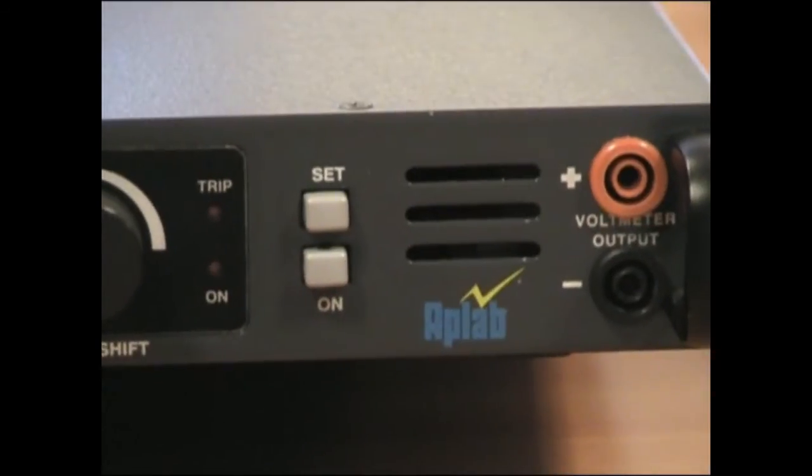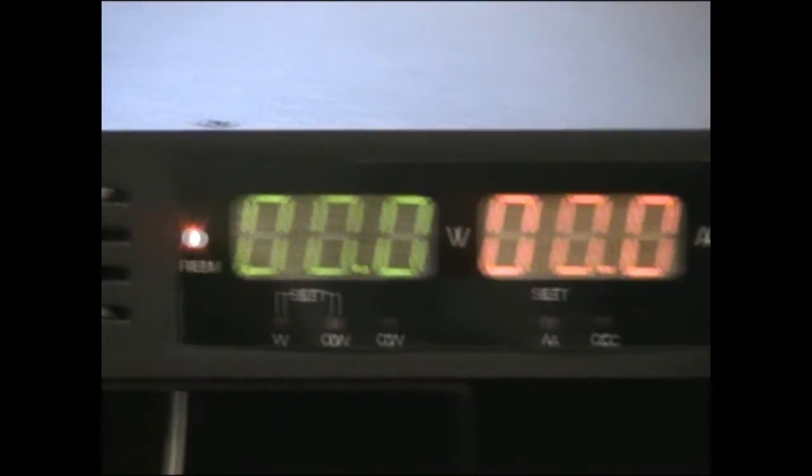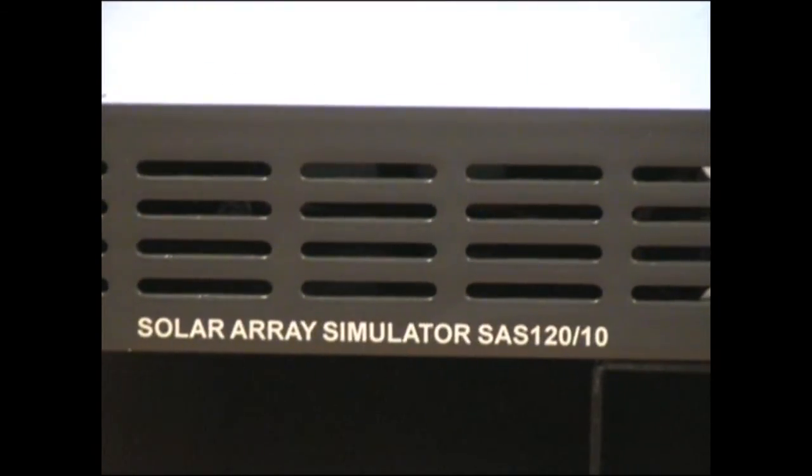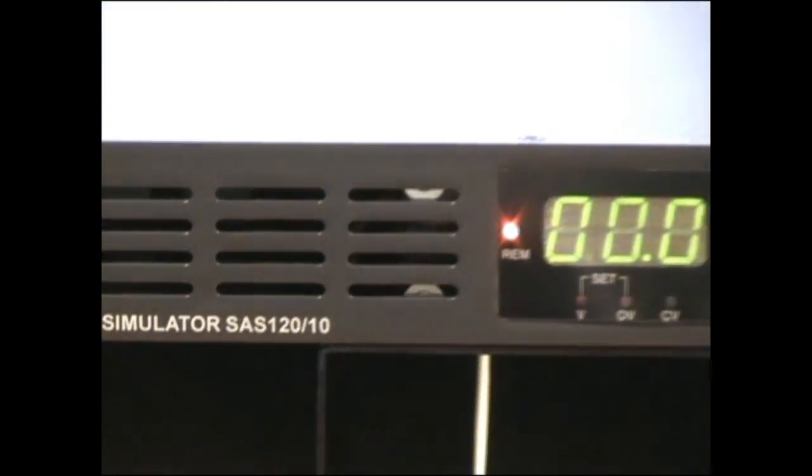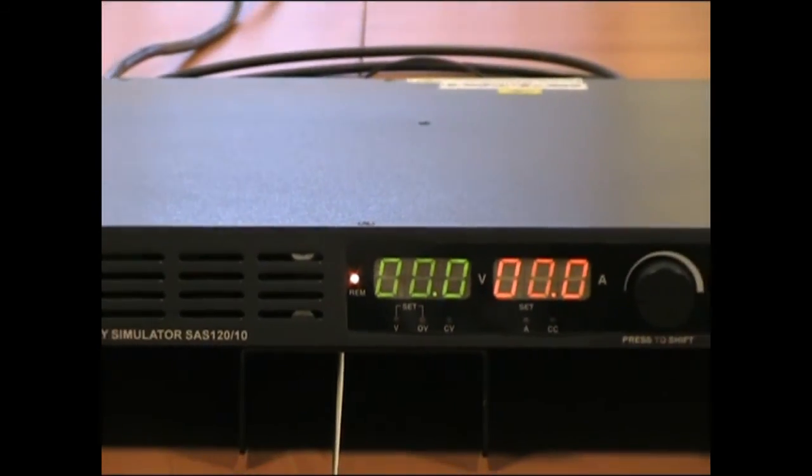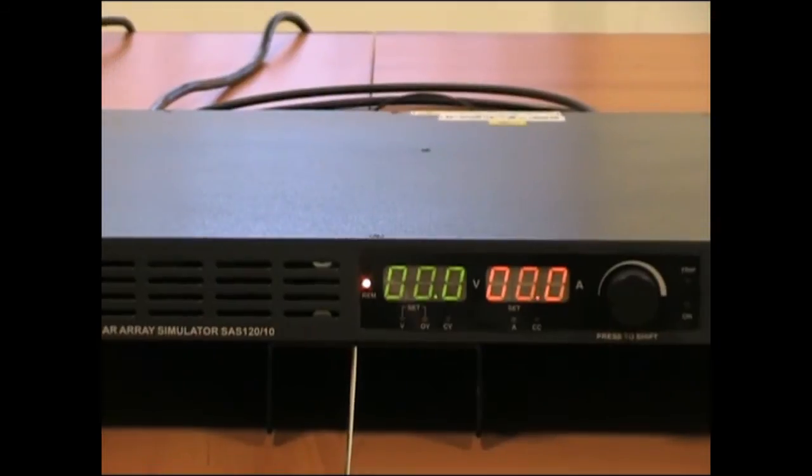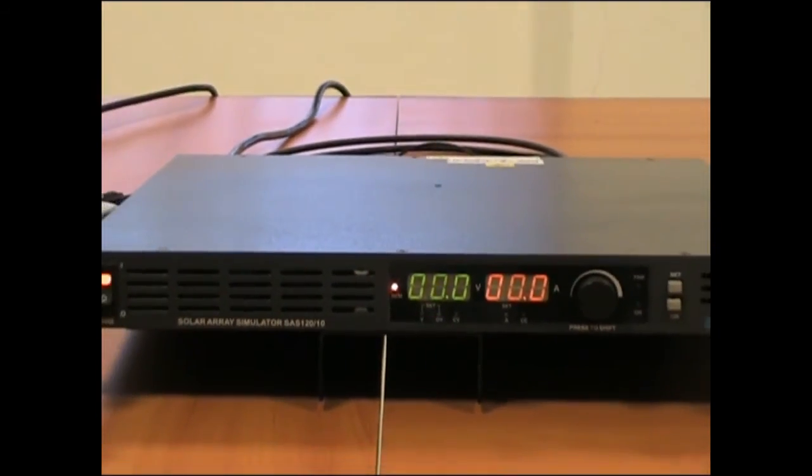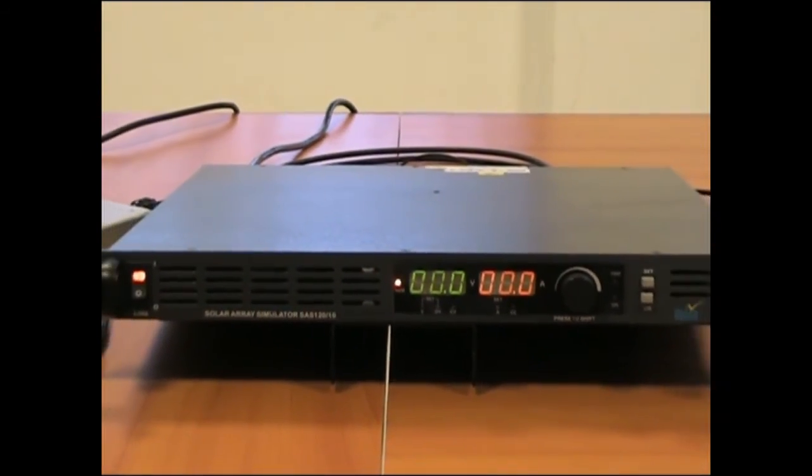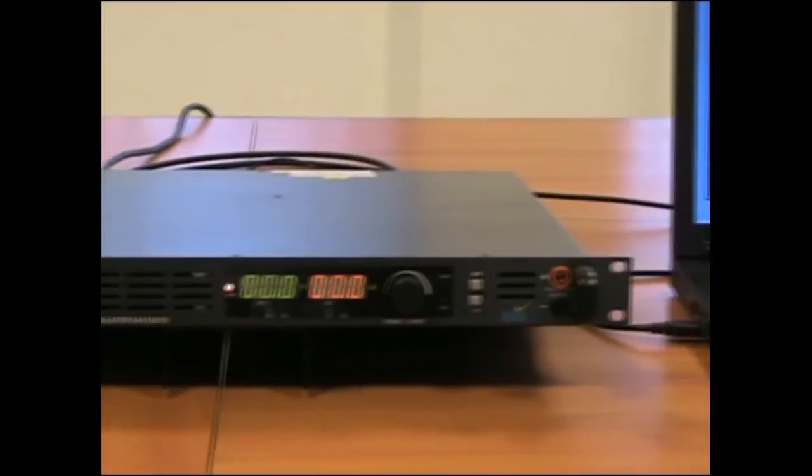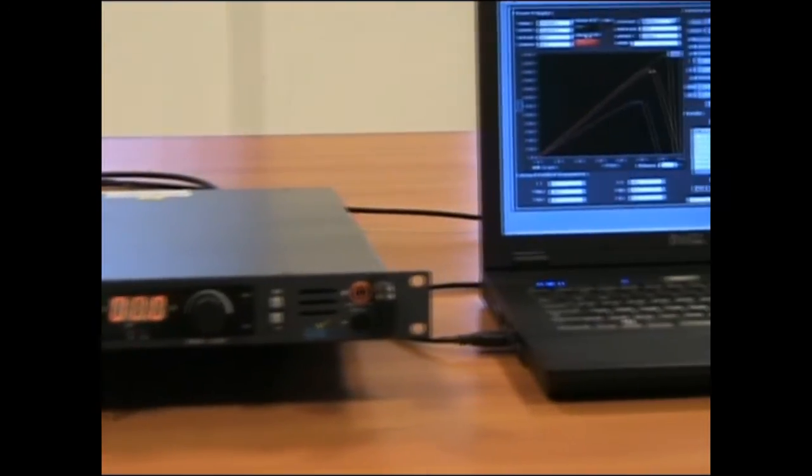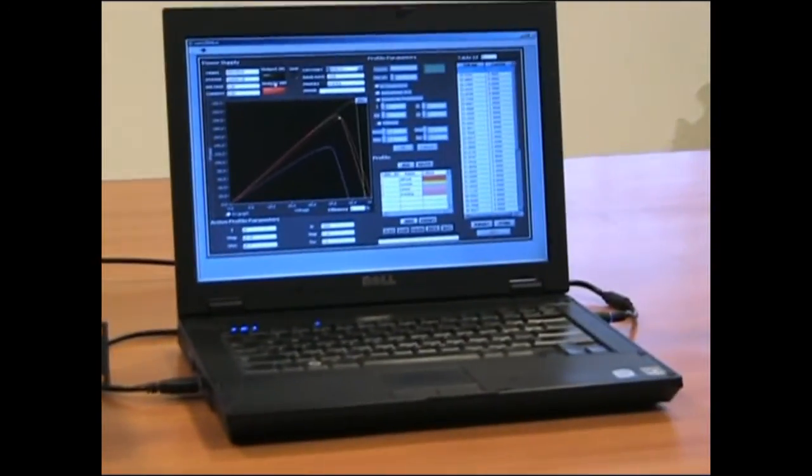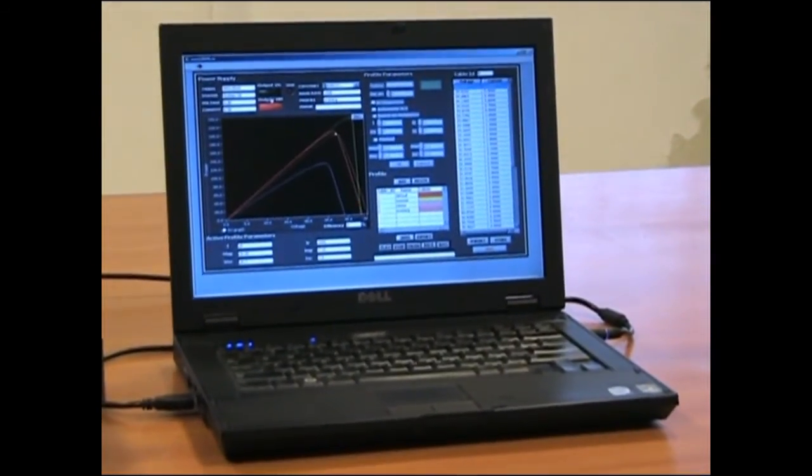The SAS120/10 is primarily a current source with very low output capacitance which is capable of simulating IV curves of solar arrays under various environmental conditions like temperature, irradiance, cloud cover, etc. It has a powerful yet user-friendly graphical user interface, the soft panel for SAS.